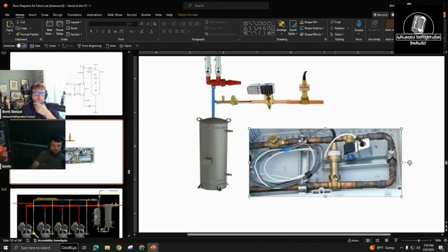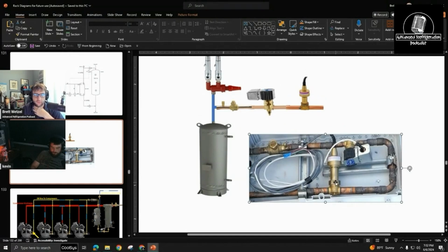This is what I was explaining before—this is a huge valve. So if this valve is running at, say, 6386 steps, that thing's going to open up 100%. It's going to take a long time. So by the time it reacts, it's already halfway there, and it'll take an additional X amount of seconds to get back.